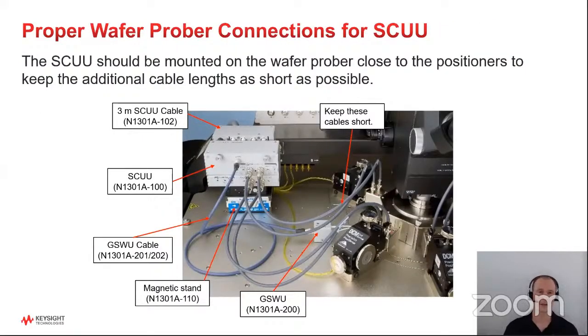This slide summarizes what I talked about. It shows the proper connections you should have if you're using our SMU-CMU Unify Unit, SCUU, with the wafer prober. You can see there's this 3-meter cable that runs off and goes to the instrument. And that cable is compensated for automatically, so you don't have to worry about compensation on that. The SCUU, you then want to mount on the wafer prober, and we have a magnetic stand that you can get. It's shown in the picture as well. And that's really nice because otherwise it prevents the cable from flopping over. Makes a nice stable thing.